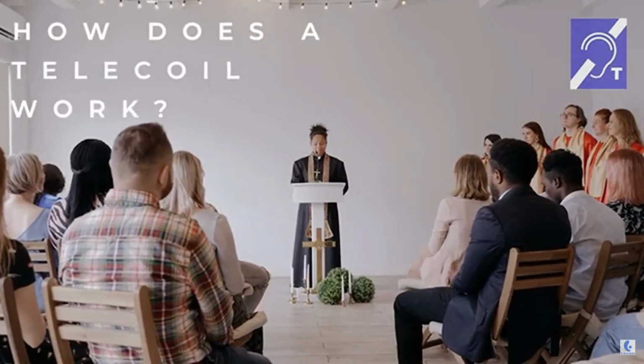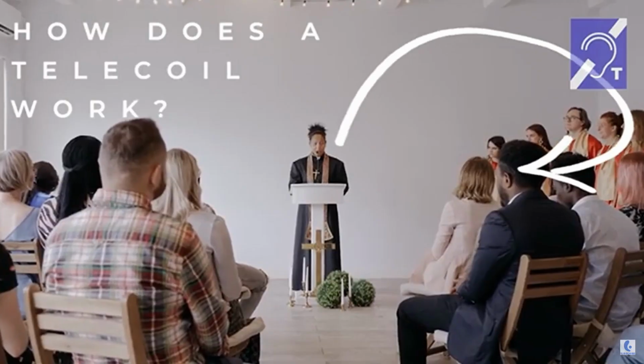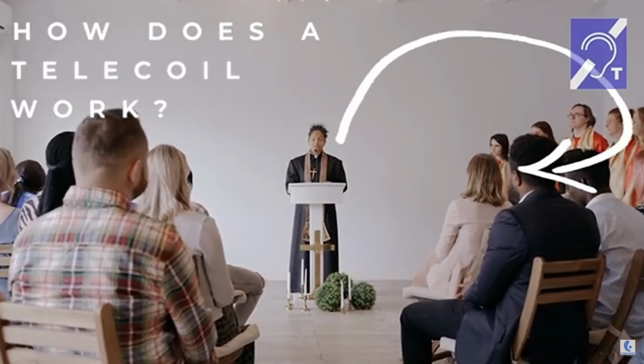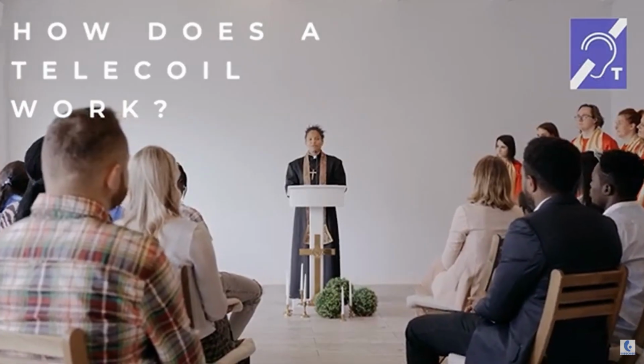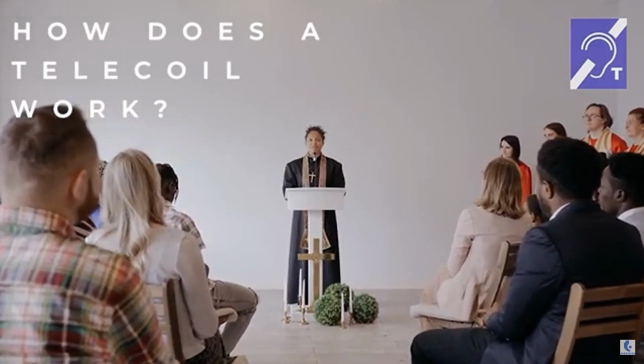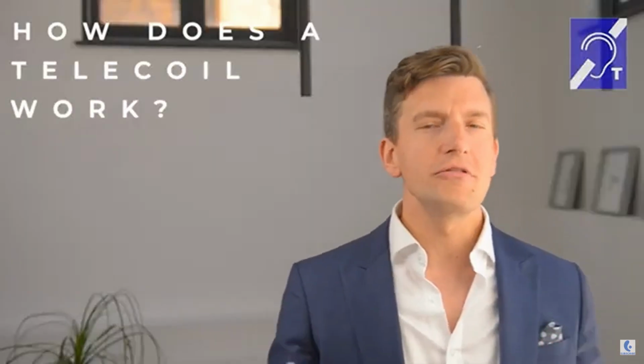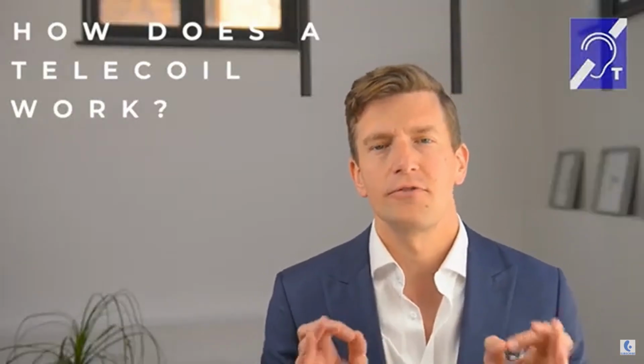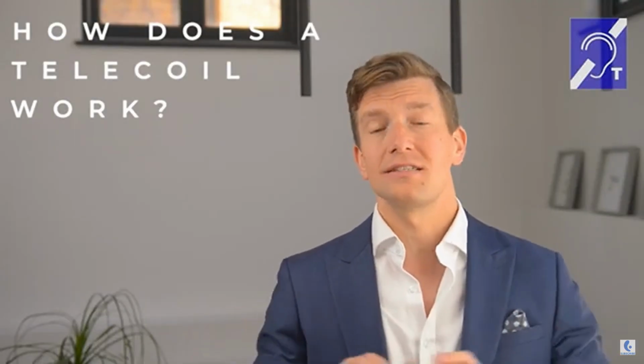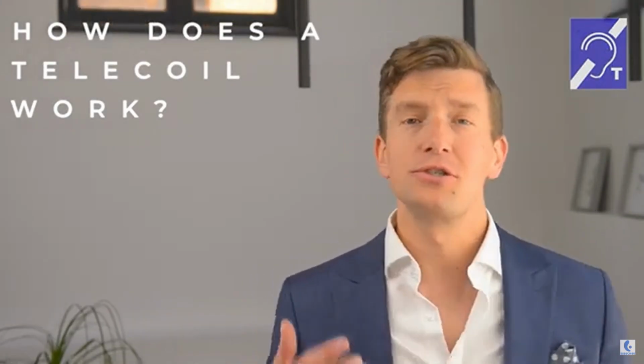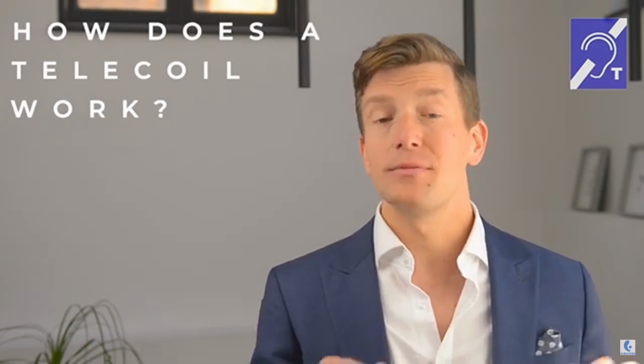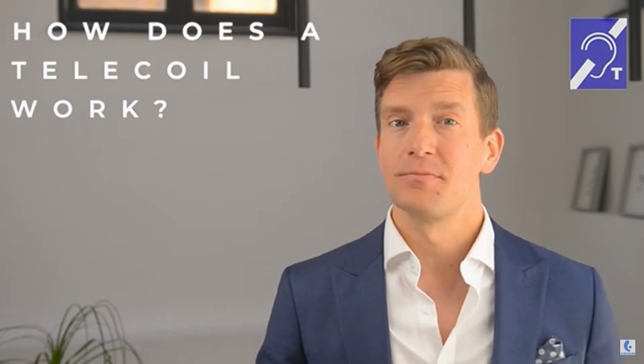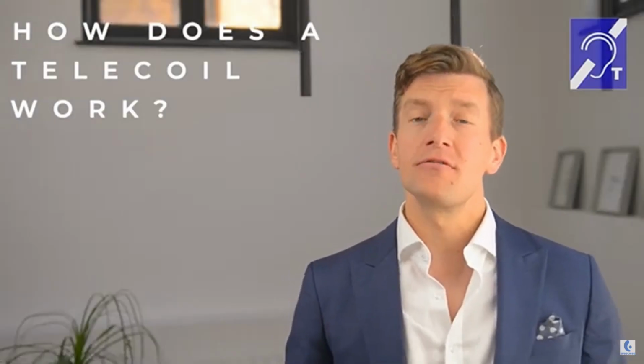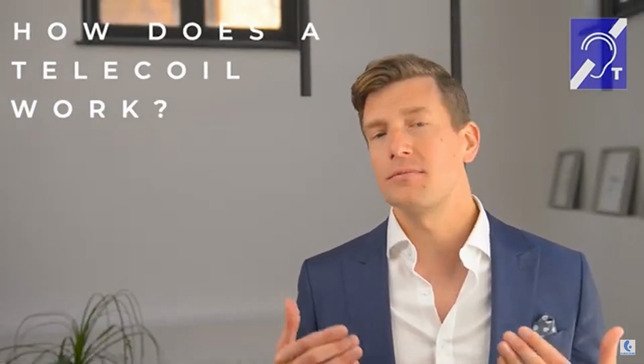This means that if a hearing aid user is in church, for example, and there's a microphone at the altar, the voice of the person speaking is then sent to the user's hearing aids and doesn't have to travel the entire distance via sound waves to the hearing aid microphones. This would give you, the hearing aid user, the feeling that you're sat in the front row no matter where you're sat in the entire church. As a result, this reduces the level of environmental noise for the hearing aid user, making it easier to hear from a distance and also in background noise. There's also no limit to the number of hearing aid users that can connect to a loop system at once.